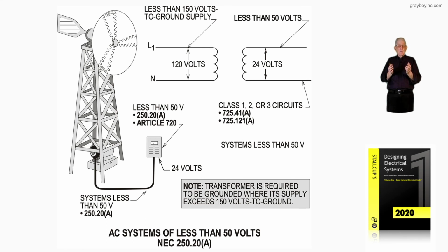And they are defined in Article 100 of the NEC. So that's what the note's telling you, that the transformer's primary cannot be more than 150 volts to ground. Then you wouldn't have to ground the secondary. But if you brought in 277 volts and fed that transformer that you see in the illustration, that's more than 150 volts to ground, so you'd have to ground the secondary. That's what this illustration is pointing out, when you would have to ground the transformer of low voltage and when you would not. And we're talking about less than 50 volts is low voltage. Basically they're calling that now the limited energy voltage. There's a limitation to it. And that's what Figure 16-15 is pointing out.